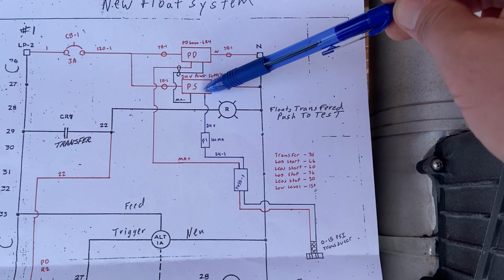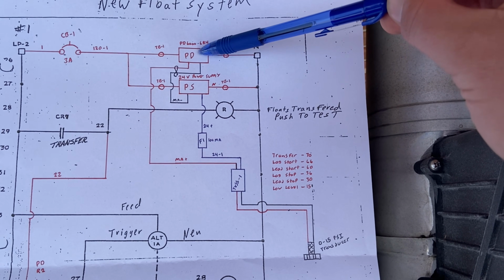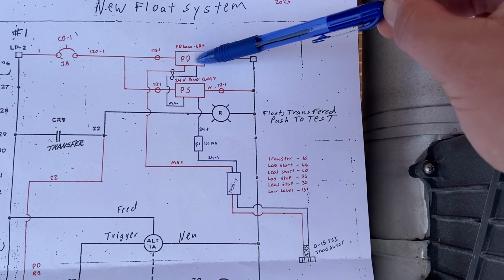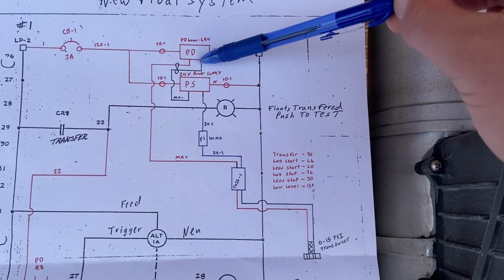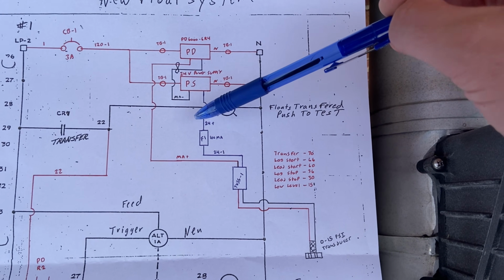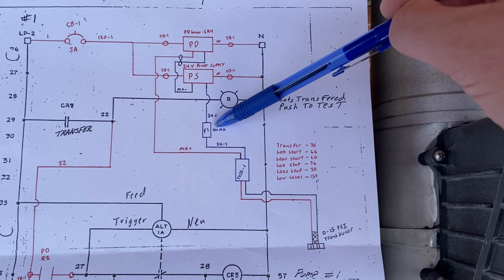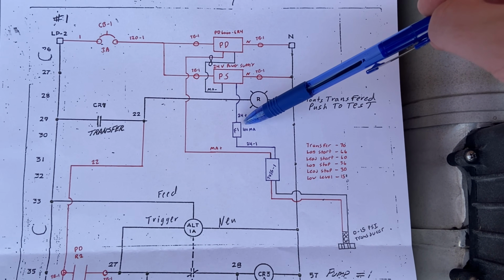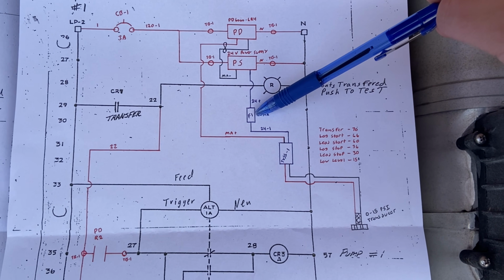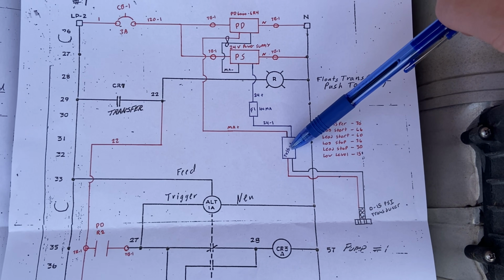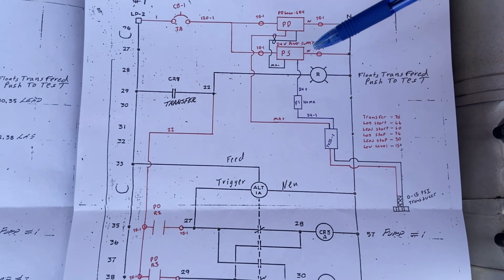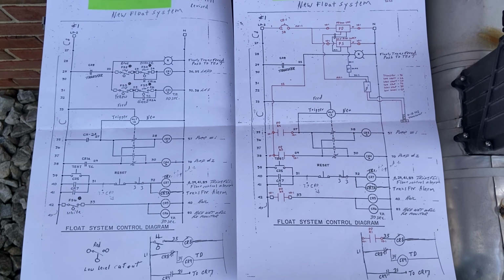So this precision digital is actually capable of powering the milliamp loop. You don't have to use a separate power supply, but we oftentimes do because it gives you a little bit more redundancy, and in some ways it helps you troubleshoot things. Same goes for the fuse and the surge suppressor. They're not completely necessary, but it just adds redundancy. It's always nice to have a fuse because you can just remove it and isolate the circuit if you want to work on something, because you can short out these milliamp loops and burn something up. So always good to be able to isolate.